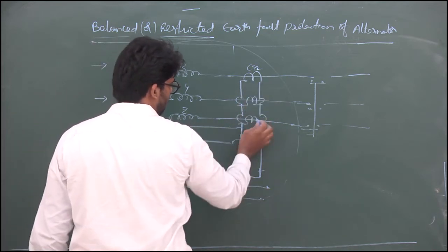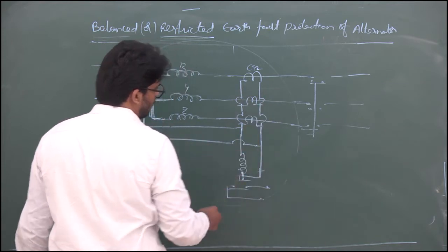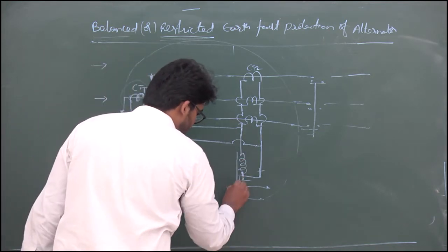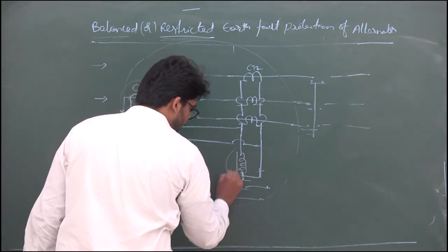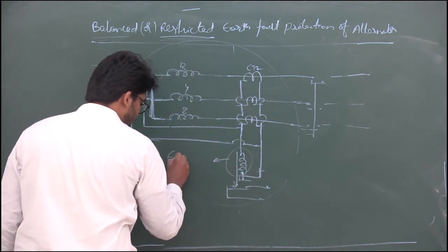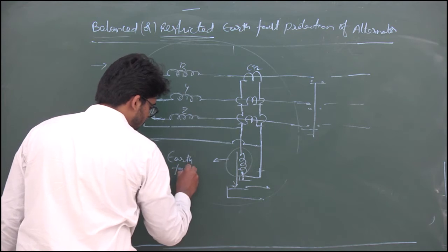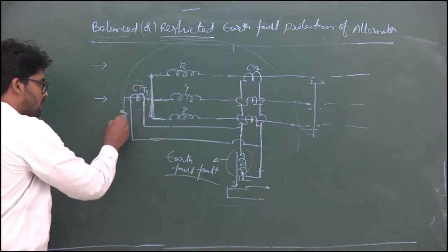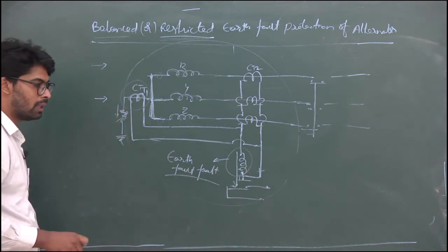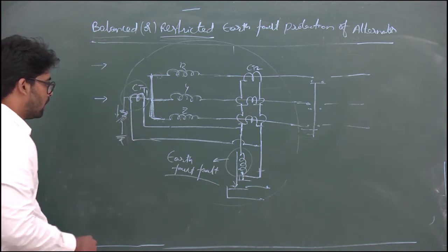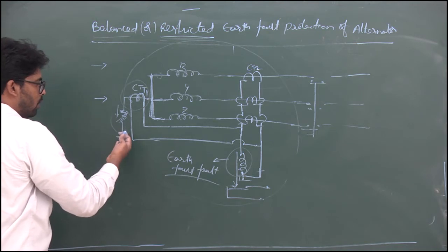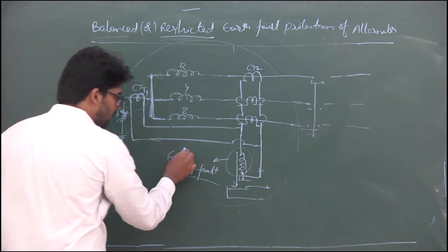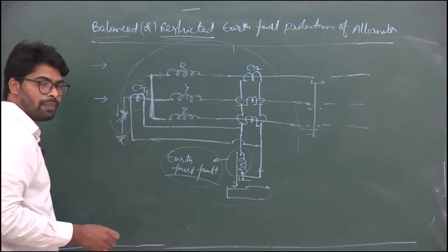The secondary is normally wired in a particular form. The relay coil in this configuration is an earth fault relay. The importance of the resistance here is that if a fault current occurs that is more than what the CTs can withstand, and the fault current is generally limited by this resistance, then this relay coil will be operated to isolate the fault section.